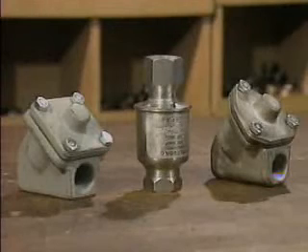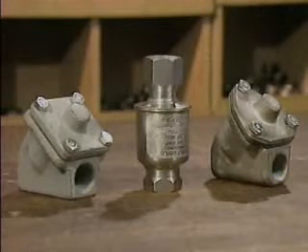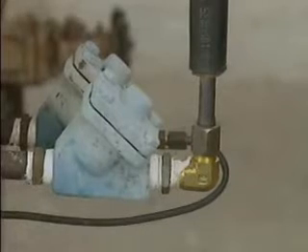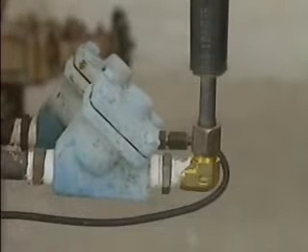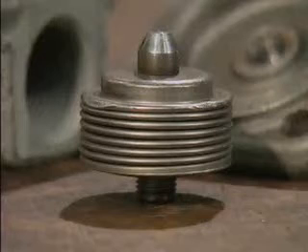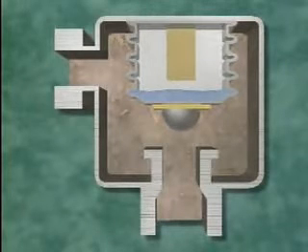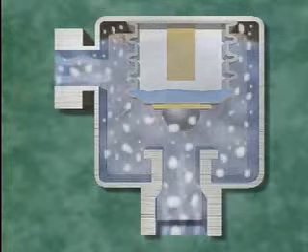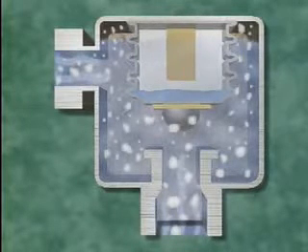In this part, we'll look at the operation of thermostatic steam traps. A thermostatic trap operates in response to the differences in temperature between steam, condensate, and air. One of the most common types of thermostatic traps is a bellows trap, which gets its name from the thermostatic bellows that is the trap's main internal component. At startup, the bellows is fully contracted and the trap valve is wide open. Condensate and air are pushed ahead of the steam directly through the trap outlet.